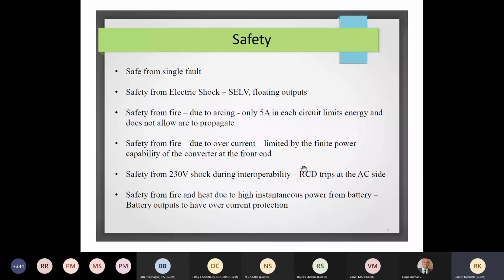The only issue with batteries is that they can supply extraordinarily high currents, and it creates two things. It can cause arcing as well as fire. The way in which we have addressed both arcing and fire is that if you are going to have a maximum of 5 amps per circuit on a 48 volt system, there is going to be arcing, but the arc does not sustain. The arc will be quenched.